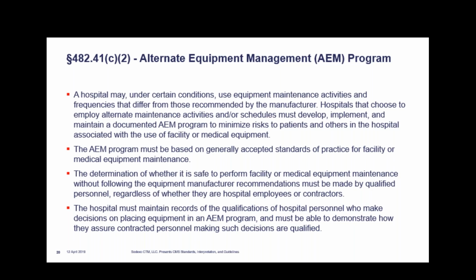We do a hierarchy where we look at the broad device description or device type when we do an AEM, which is why we also allow our sites to cater it more towards their specific model. If they have a model that breaks down more frequently than what we've noted as the reliability index, they can adjust it by increasing maintenance frequency or add a task to get that moving forward. The answer to your question is yes, and the reason for that primarily is because on a regular basis, you need to go back and validate that justification still exists.